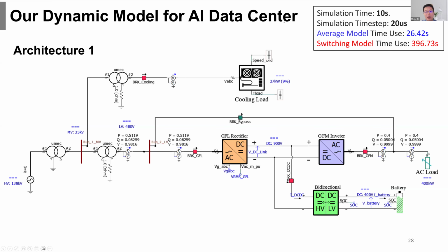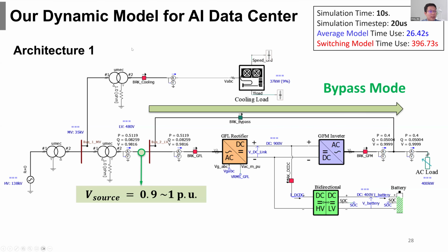And for a data center, it can operate at different operation modes, including the bypass mode, the double conversion mode, and also the battery backup mode, depending on the grid side voltage. Let me give you the examples. So suppose the grid side voltage is in the normal condition. For example, the voltage from the grid is about 0.9 to 1 per unit. This means the grid voltage is at the normal condition.